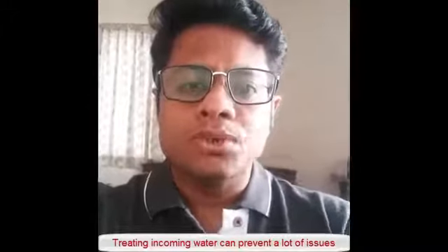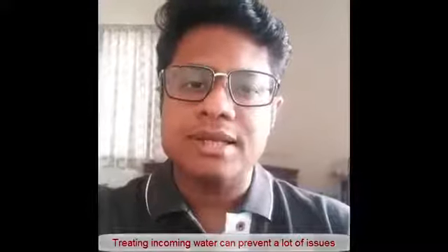When you see two cylinders, the standard ones are a sand filter and a carbon filter, together with a softener sometimes. The first cylinder you generally see is a sand filter, which is to reduce the turbidity of the incoming water. If the water is not clear, the sand filter will reduce particles and make it a little clearer. They use different grades and sizes of sand so the particles are filtered. However, for higher turbidity, there are different materials available for filtration.